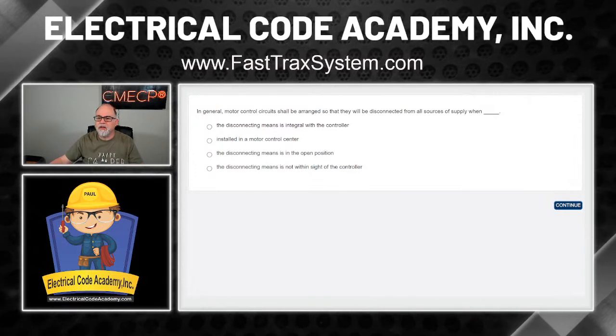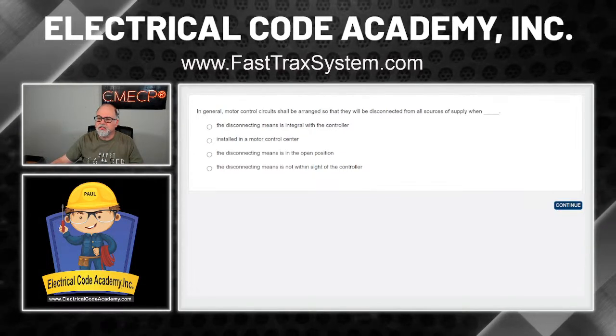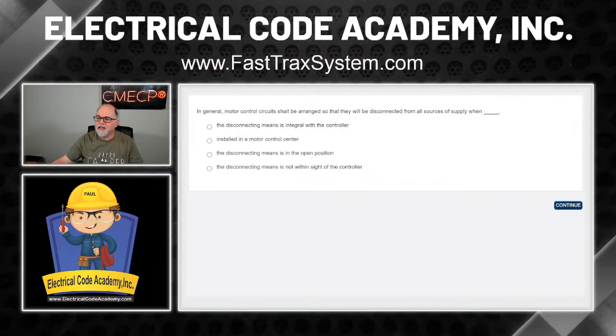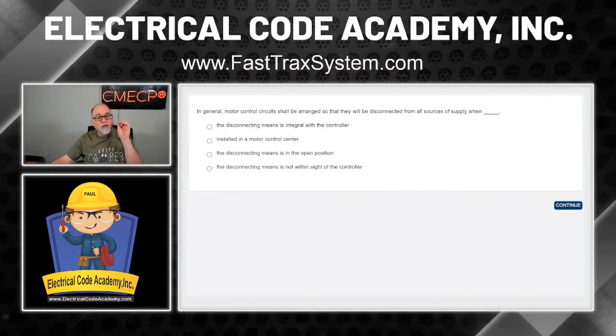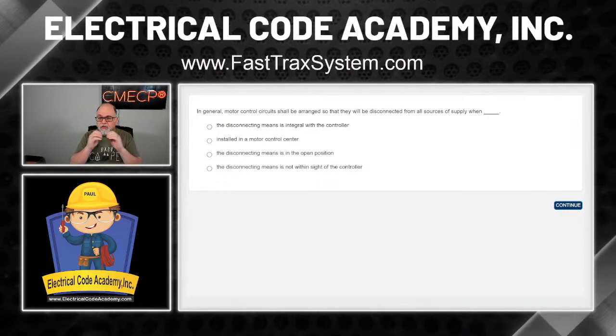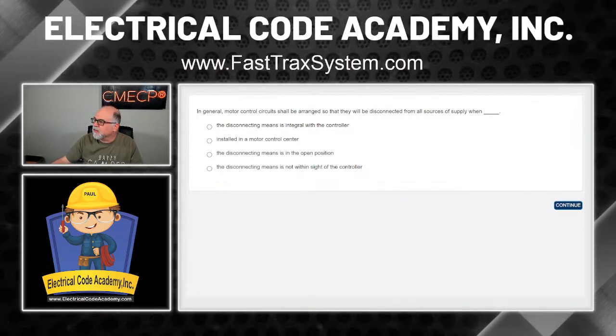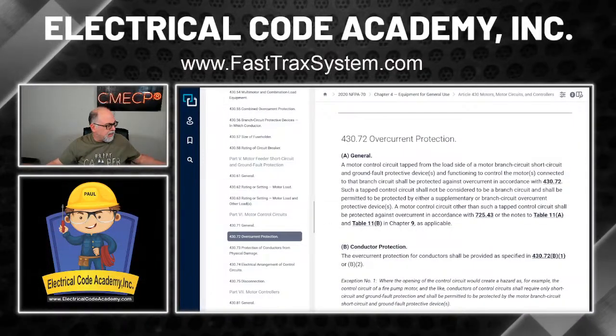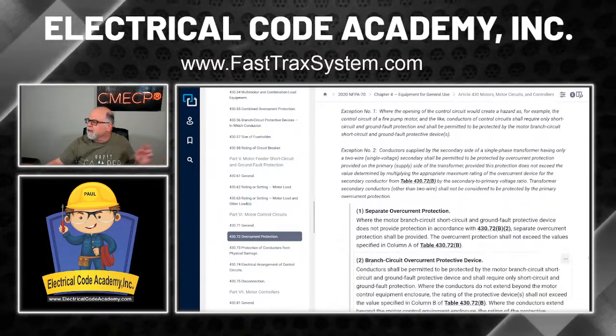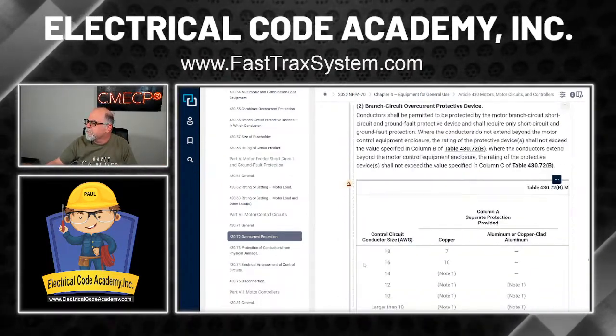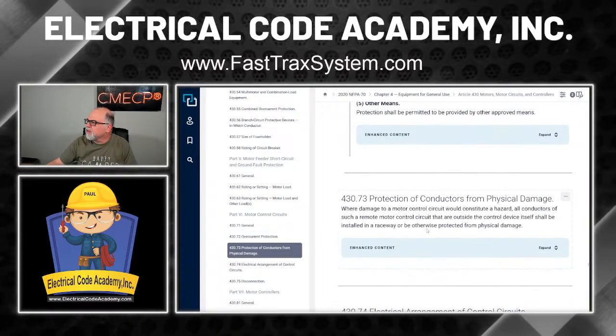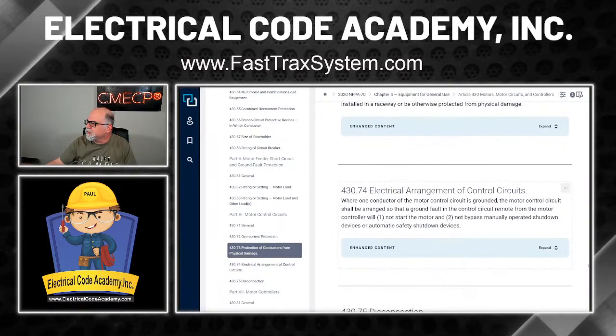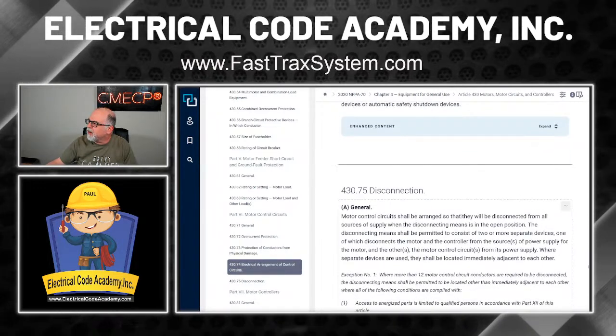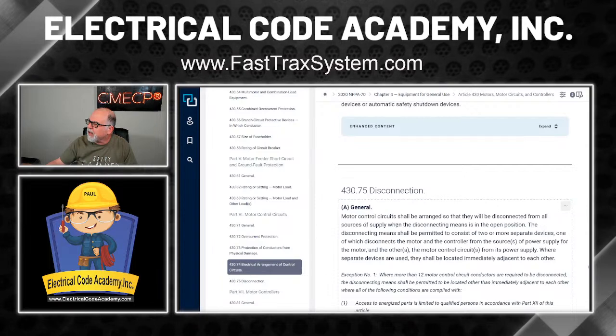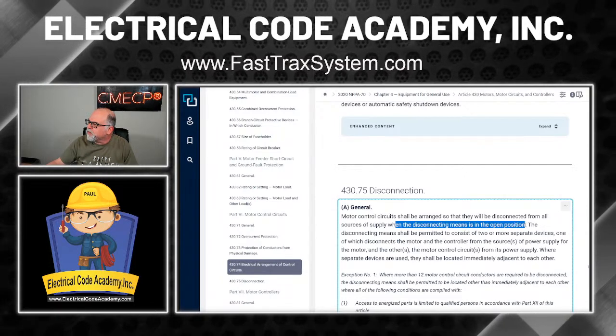All right, so back at our question, it says, in general, motor control circuits shall be arranged so that they will be disconnected from all sources of supply. Okay, so that phrase, arranged so that we disconnect from all sources of supply. So let's go back over to the code real quick and see if we can figure that out. So bear with me while we go look. And we're back over here. And here's control circuit conductors, arrangement of disconnection. Motor control circuits shall be arranged so that they will be disconnected from all sources of supply when the disconnecting means is in the open position.